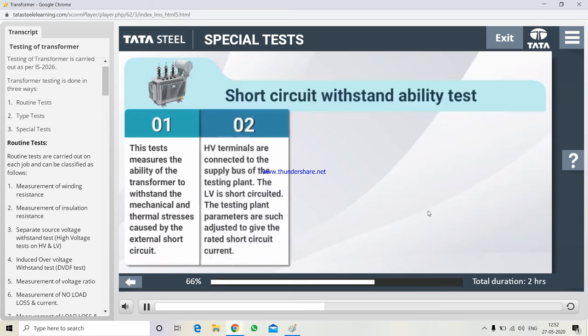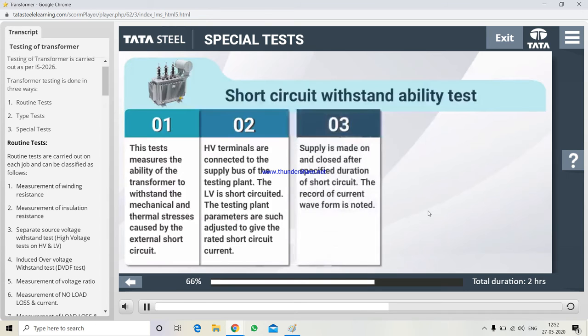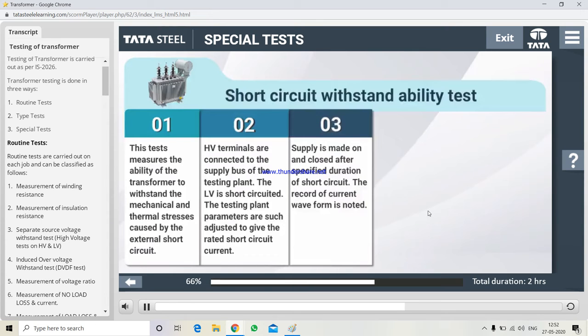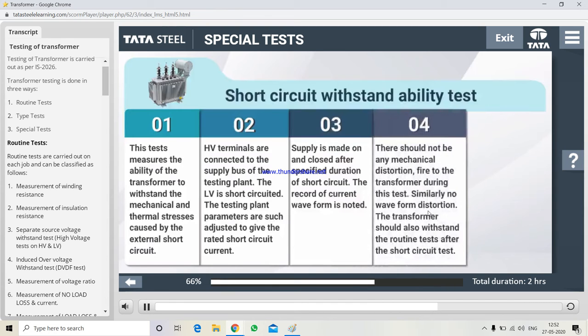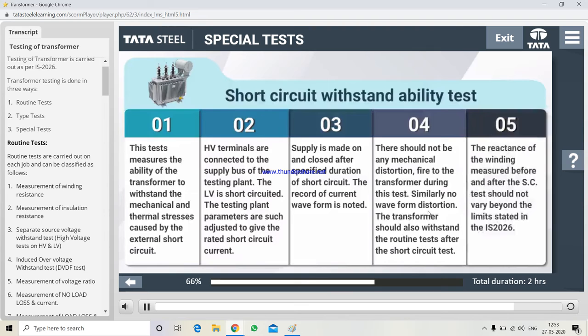HV terminals are connected to the supply bus of the testing plant. The LV is short-circuited. The testing plant parameters are adjusted to give the rated short circuit current. Supply is switched on and closed after the specified duration of short circuit. The record of current waveform is noted. There should not be any mechanical distortion of the transformer during this test. Similarly, no waveform distortion. The transformer should also withstand the routine tests after the short circuit test. The reactance of the winding measured before and after the SC test should not vary beyond the limits stated in IS 2026.